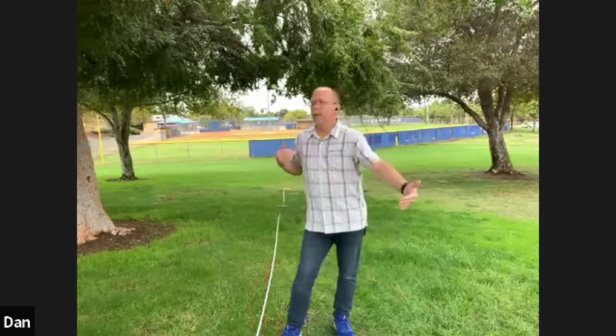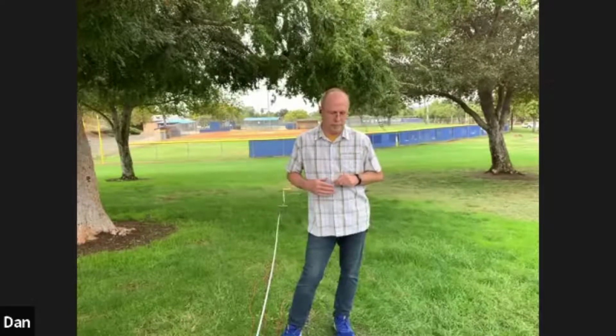Now, the other thing we're looking for is a variance of no more than 5% between our three readings. Because if we see dramatic readings, there's a problem either with our probe placement or our ground placement, or there's some other technical problem. If I had a 50% drop off between those readings, we'd need to throw those out and redo the test. So we're only looking for 5% variance. Okay, so that was our second reading.